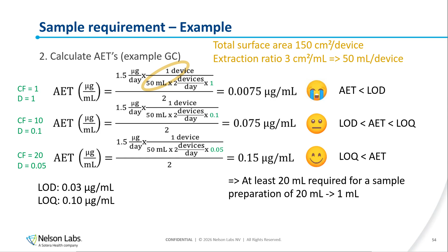Next up, I have increased the concentration factor to 10, meaning the D is 0.1, and of course it just increases by 10. But we're not yet at LOQ level. Now we're in between both, meaning that quantification for some compounds will not be good. So we will keep going, and now we're at a concentration factor of 20, and we are above the LOQ, which is fine. But because we need to do a preparation then from 20 milliliters, for example, 20 to 1, we need at least 20 milliliters already for just this technique and this analysis.